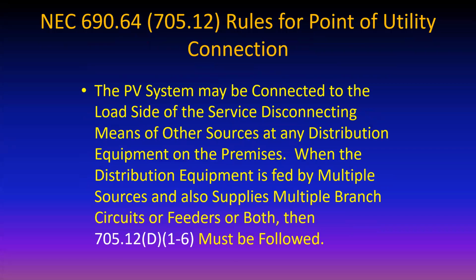If you go to 690.64, which is the same as 705.12 now, but once upon a time it used to be 690.64, there's lots of rules for where you can connect to make this point of utility connection, okay? And here you can read this. You can connect to the load side of the service disconnecting means, or you can connect to the line side of the service disconnecting means. You just need to follow proper tap rule connections. And you follow 705.12 D 1 through 6, and that gets you there.